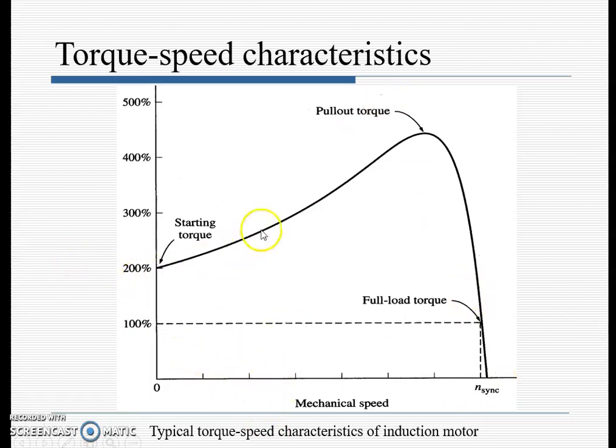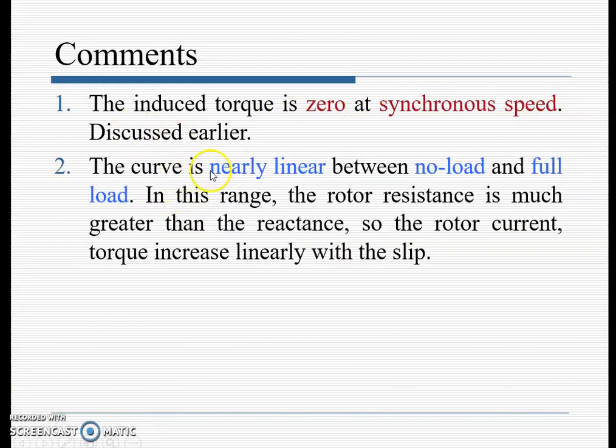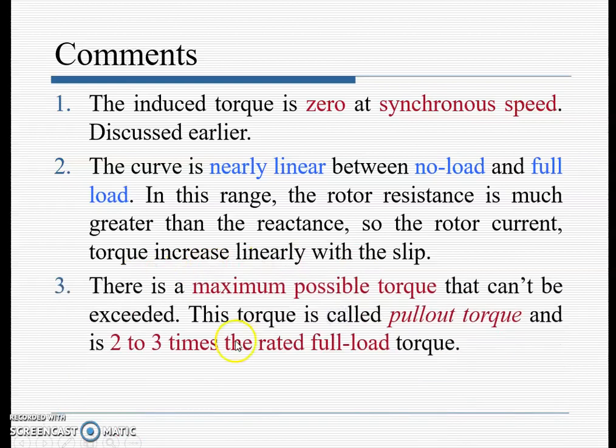The torque can increase up to about 400% of full-load torque. The induced torque is zero at synchronous speed. The curve is nearly linear between no-load and full-load; in this range, rotor resistance is much greater than reactance so rotor current and torque increase linearly with slip. There is a maximum possible torque called the pull-out torque, which is two to three times the rated full-load torque.